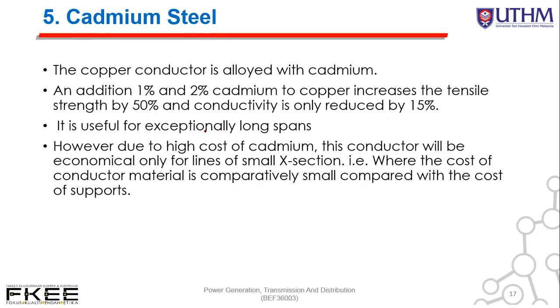Now let's see the cadmium copper. The copper conductor is alloyed with cadmium. Adding 1% to 2% cadmium to copper increases the tensile strength by 50%, but conductivity is reduced by only 15%. It is also useful for exceptionally long spans. However, due to the high cost of cadmium, this conductor will be economical only for lines of small cross-section, where the cost of conductor material is comparatively small compared with the cost of the supports.